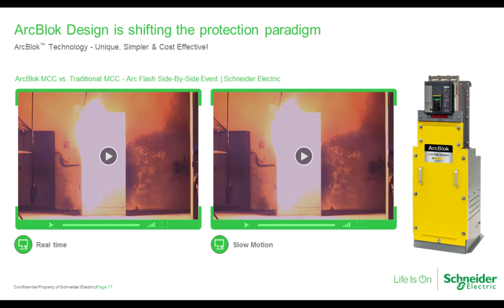Okay, so what you've seen there is the power of managing internal arcs, treating power conductor systems like their circuit breakers, limiting the energy and duration of any arcing fault, containing and redirecting any energy that is there away from the user, minimizing damage and downtime. And all this with the simplicity and reliability that comes from a passive design with no moving parts. So let's go back to Erhan now to show you some more about the commercial offer.